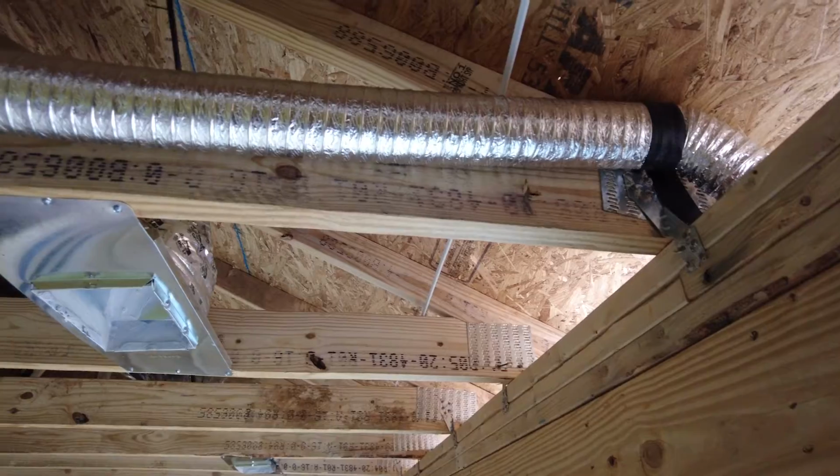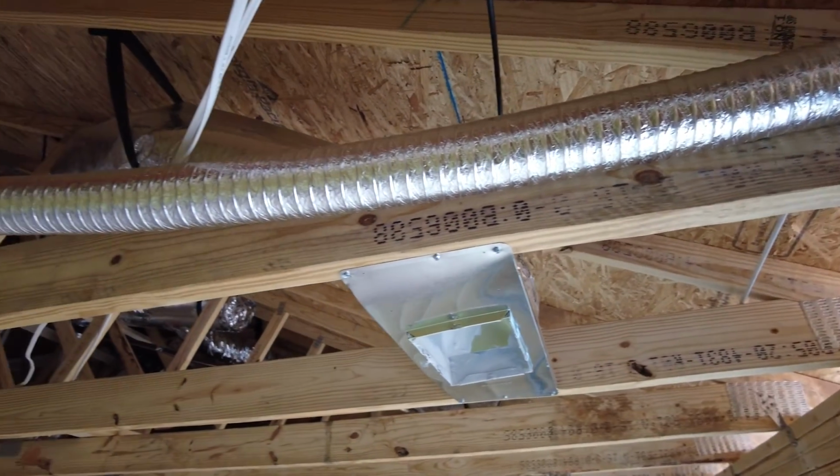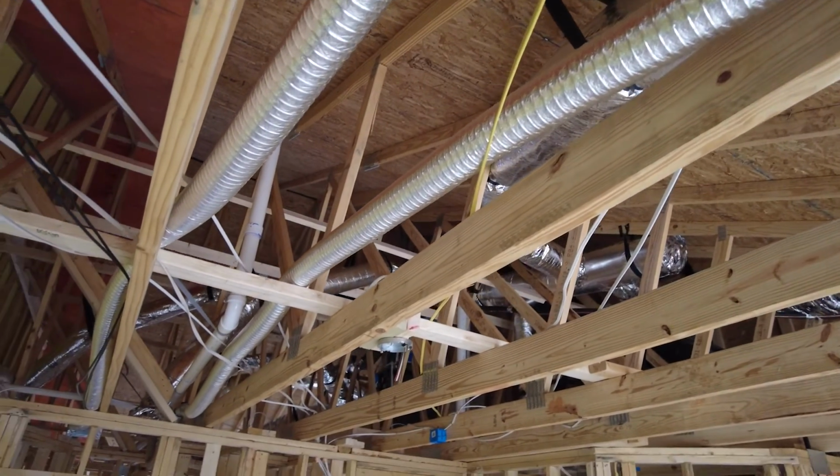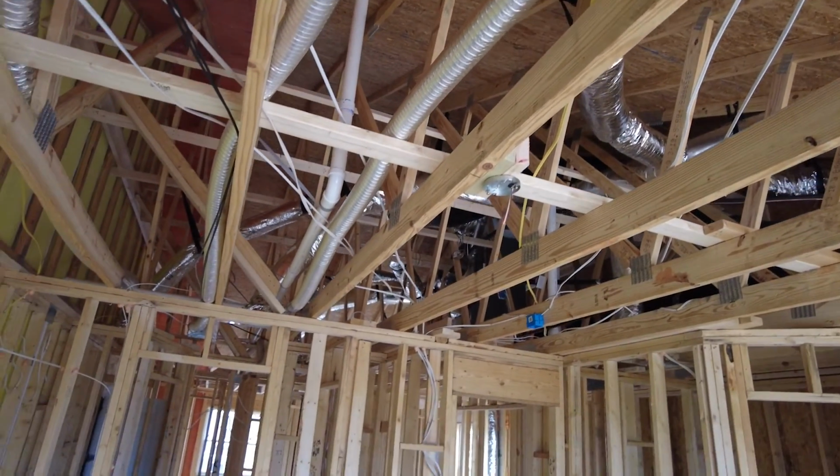Those problems are poor quality bath fans to begin with, small diameter ducts, flexible duct runs instead of hard pipe duct runs, and long duct runs, 30 feet in this case. There's no way this bath fan is ever going to perform in an adequate manner to remove humidity from this bathroom and to cut down on the issues that humidity might cause.